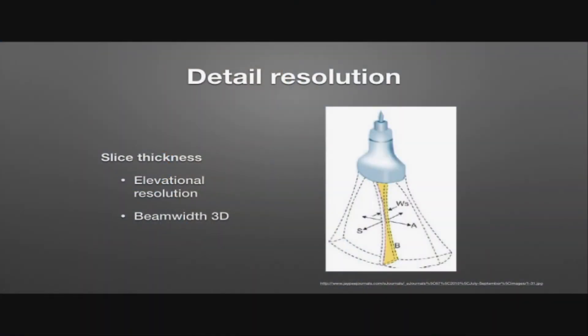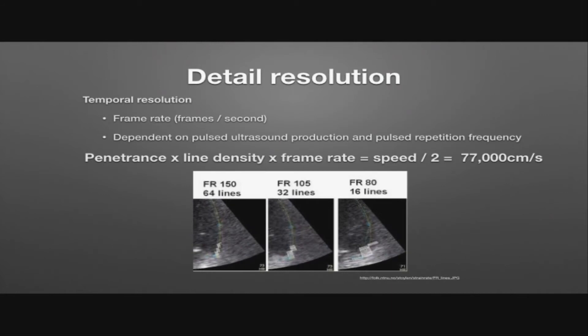Finally, in terms of trying to separate two structures, let's consider slice thickness. This is the ability to resolve two structures in the elevation of the beam width, and it reiterates the fact that the beam is a three-dimensional structure. We've got to resolve images in the axial plane, the lateral plane, and in the elevation plane. If you get a structure smaller than the elevation plane of the beam width, that's going to be able to generate an echo regardless. As well as structures separated by distance, we also need to consider structures separated in time — for instance in echocardiography, we're often looking at moving structures.